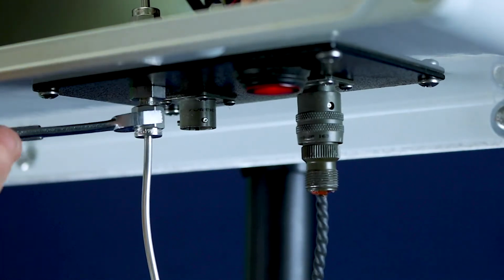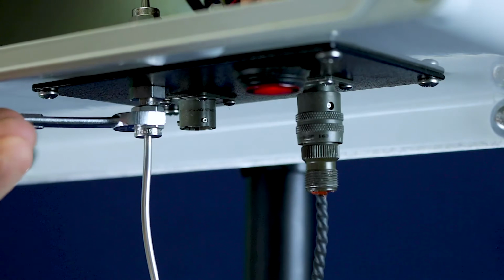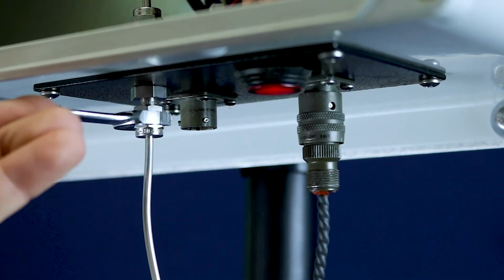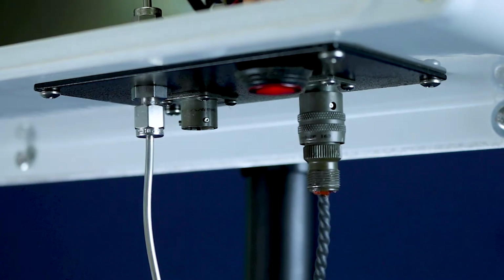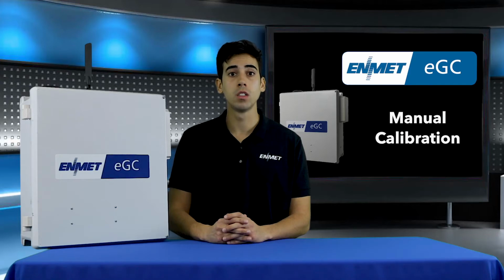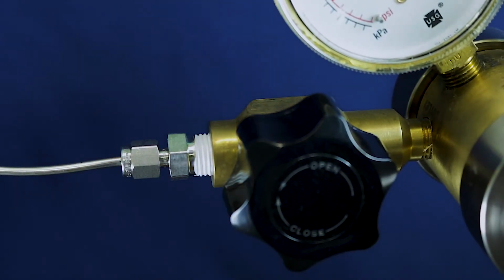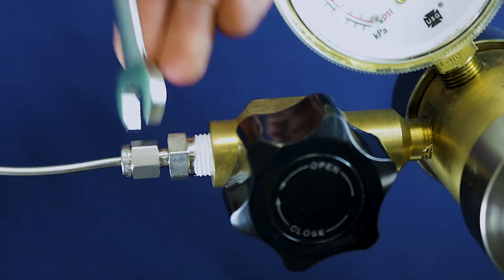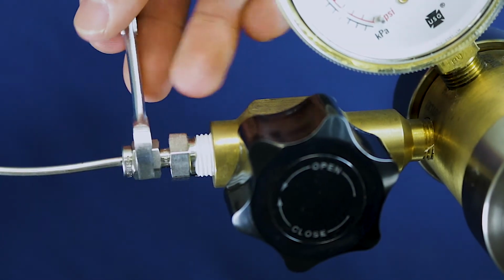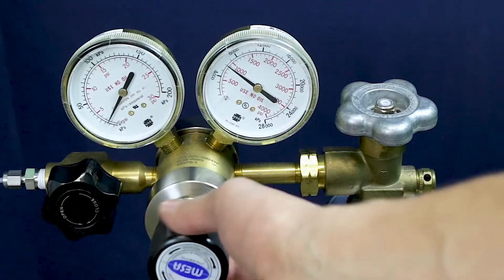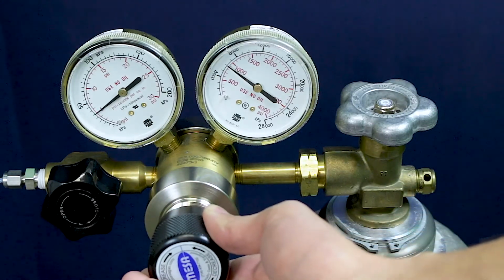The calibration gas cylinder requires a 2-stage pressure regulator with a 1/8 inch outlet fitting to connect the stainless steel tubing. Secure the pressure regulator to the cylinder. Once secured, turn on the main valve on the cylinder and adjust the second stage pressure to 5 psi.